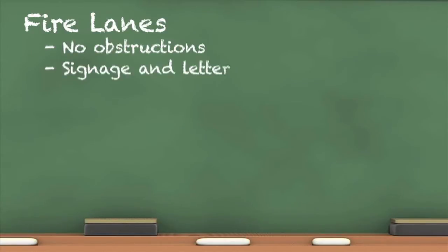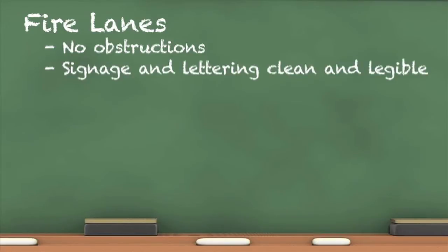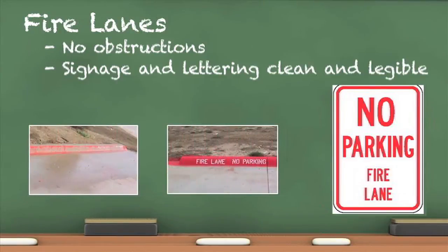Fire lanes are required to be stenciled every 30 feet or have signs every 100 feet facing traffic. The fire lane on the left is in violation of the fire code. The fire lane on the right looks great.